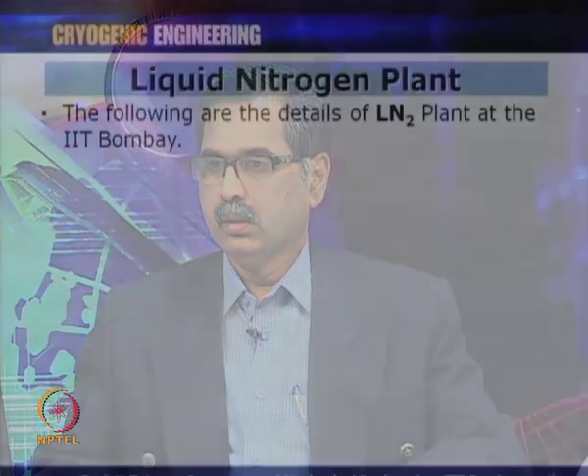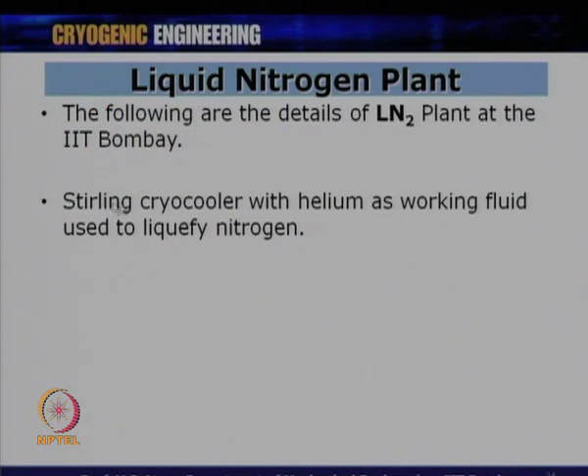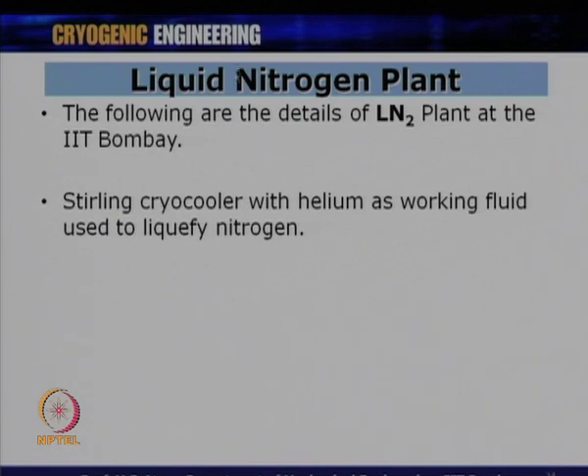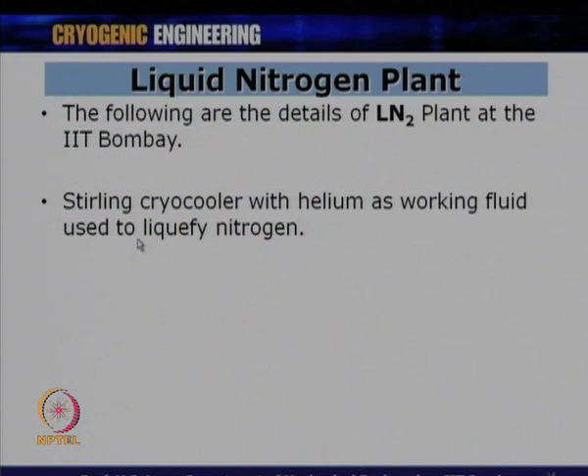Now let us see the liquid nitrogen plant at IIT Bombay. This plant uses a Stirling cryocooler with helium as the working fluid to liquefy nitrogen — it is a closed-cycle system, different from the open-loop systems studied earlier. The cryocooler generates a cooling effect at 77 Kelvin and has a condenser onto which nitrogen gas flows and gets liquefied. The working fluid helium just produces cold, while the nitrogen comes over and gets liquefied.